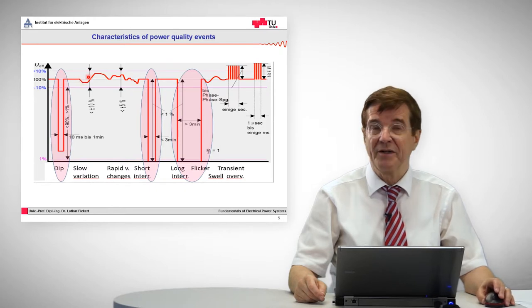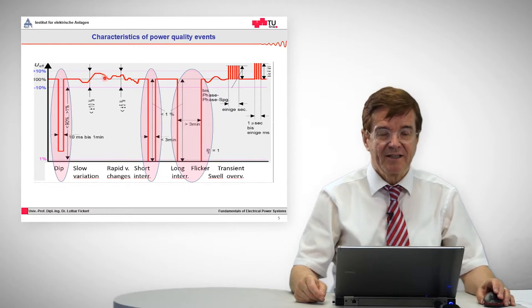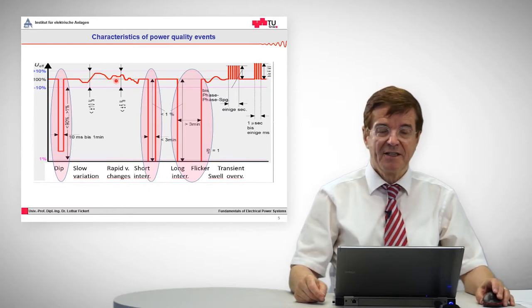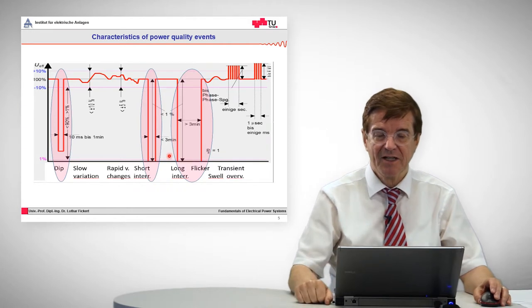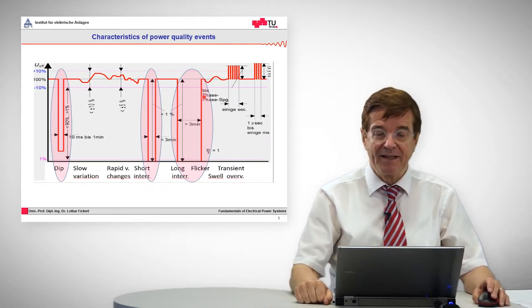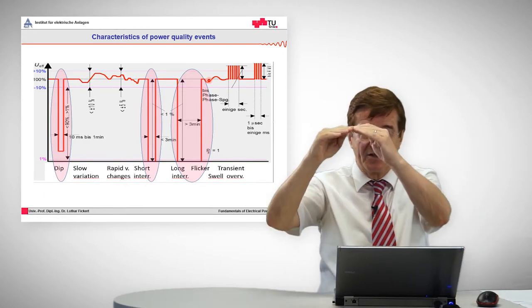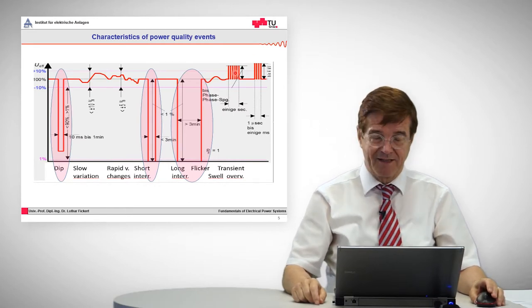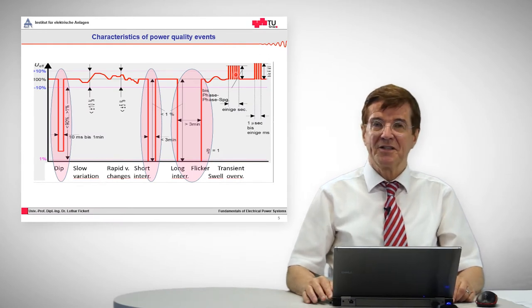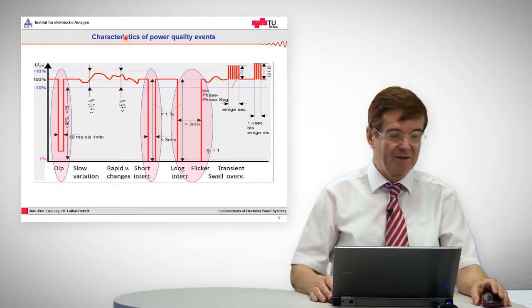Another feature is the fluctuation of voltage, where we speak about slow variation and rapid changes. There are short interruptions where the voltage is even below 1%, which is defined as the limit for interruptions. We also have longer interruptions. Then there may be something like flicker, which is periodic variation of the voltage. There may also be transient overvoltages, swells and sags. These are the features where the voltage is not perfect, and these are the characteristics of power quality events.